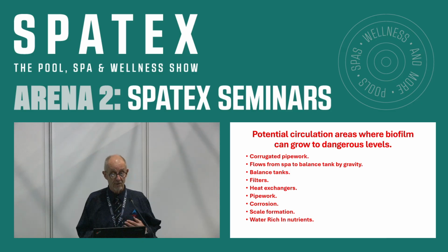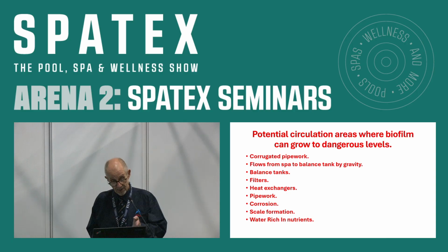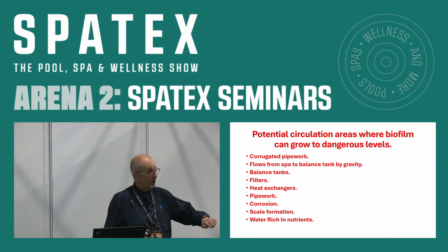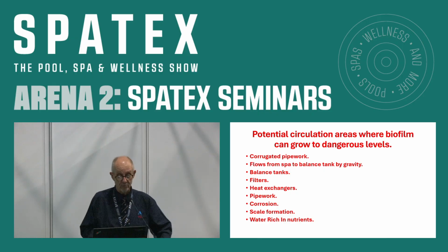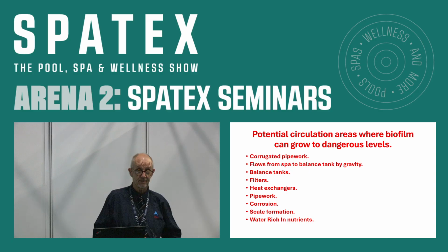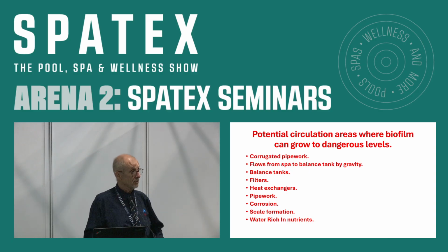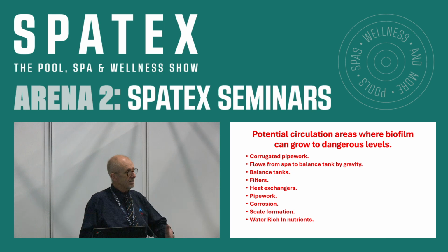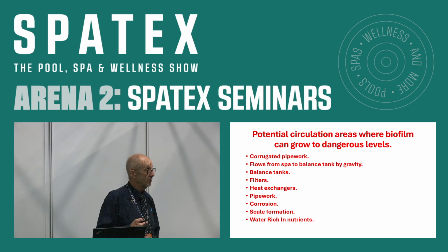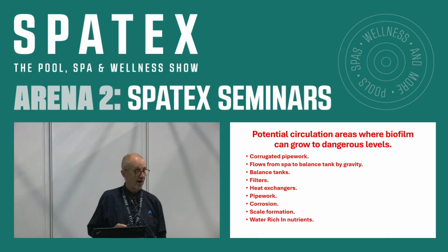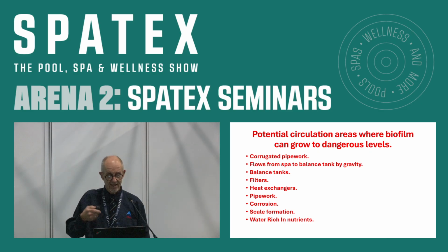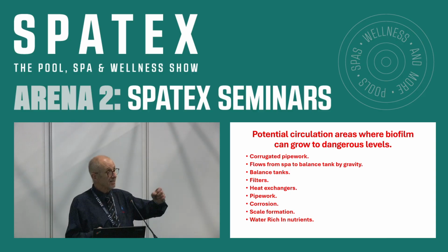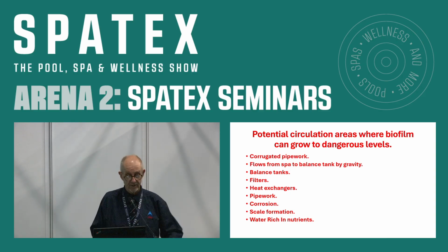Potential areas where biofilms grow: corrugated pipework, flows from the spa to the balance tank, which is just by gravity. So you've got a very slow flow in that pipework. The corrugated pipework is classic for some of these spas that they import from other countries. And in that journey, bringing the spas over here from, say, places like China, it's got plenty of time to be static, and these biofilms are growing. So when you first open your new spa, you should make sure it's disinfected and cleansed before you use it the first time, and take a microbiological test result and wait for it to come back.